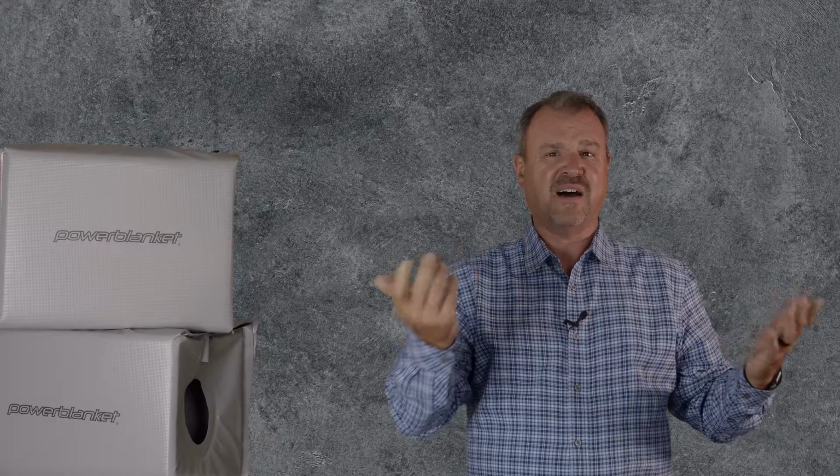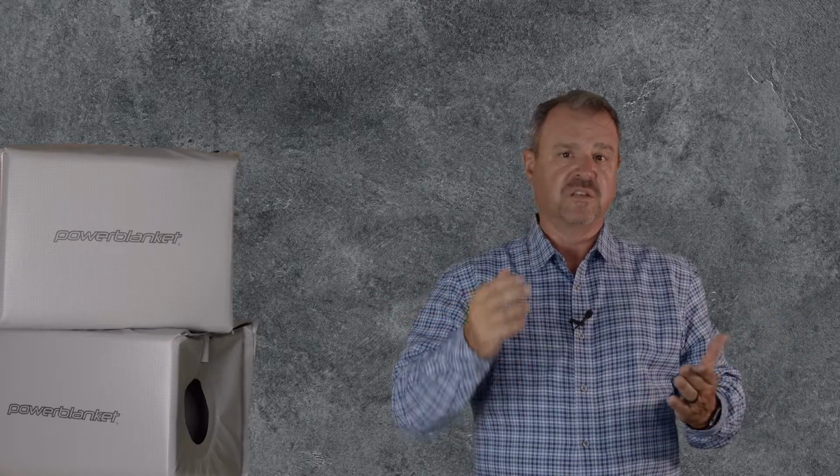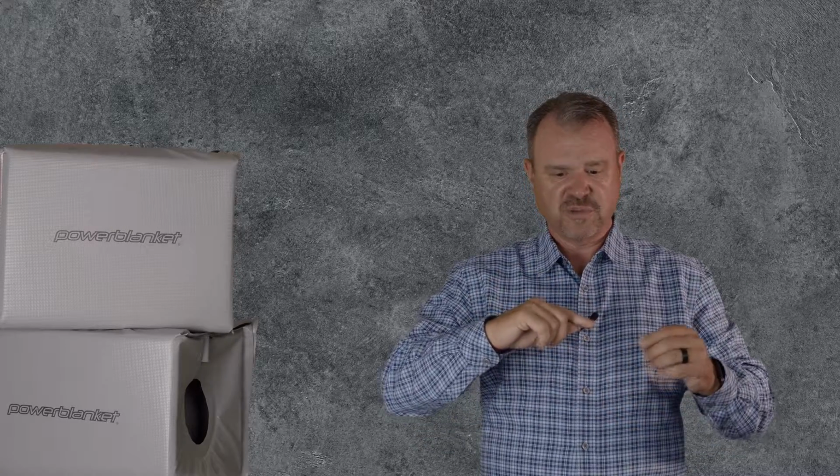Corrosion is another thing that occurs in electric process heaters. Because you're heating chemicals or there's product around that can corrode the heating elements, it's really important to pull that heater out. Realize that the electric heating element is the hottest part of the process. So the hottest part always gets attacked first. What you want to look for is pitting or some sort of a corrosion or a white corrosion or a thinning of the element.